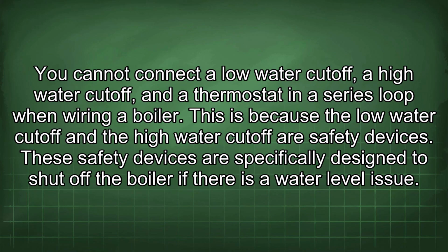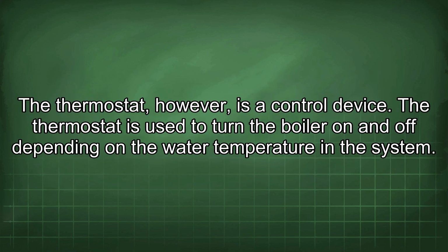You cannot connect a low water cutoff, a high water cutoff, and a thermostat in a series loop when wiring a boiler. This is because the low water cutoff and the high water cutoff are safety devices. These safety devices are specifically designed to shut off the boiler if there is a water level issue. The thermostat, however, is a control device. The thermostat is used to turn the boiler on and off depending on the water temperature in the system.